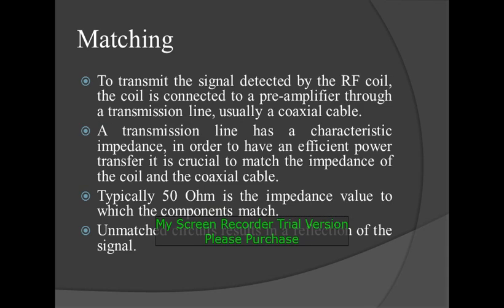Matching: to transmit the signal detected by the RF coil, the coil is connected to a pre-amplifier through a transmission line, usually a coaxial cable. A transmission line has a characteristic impedance. In order to have effective power transfer, it is crucial to match the impedance of the coil and the coaxial cable. Typically, 50 ohms of resistance is the impedance value to which the components are matched. Mismatched circuits result in a reflection of the signal.